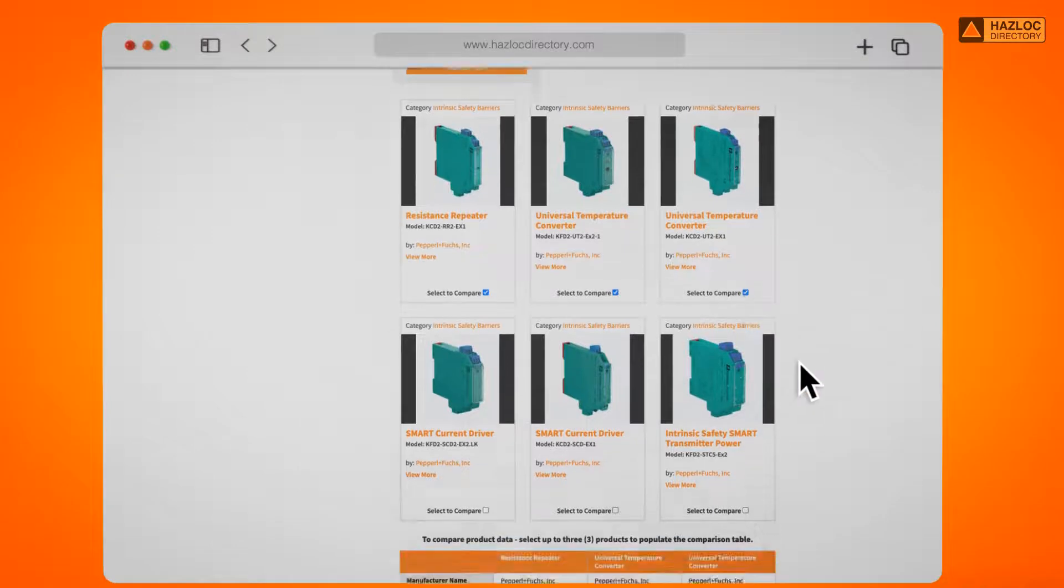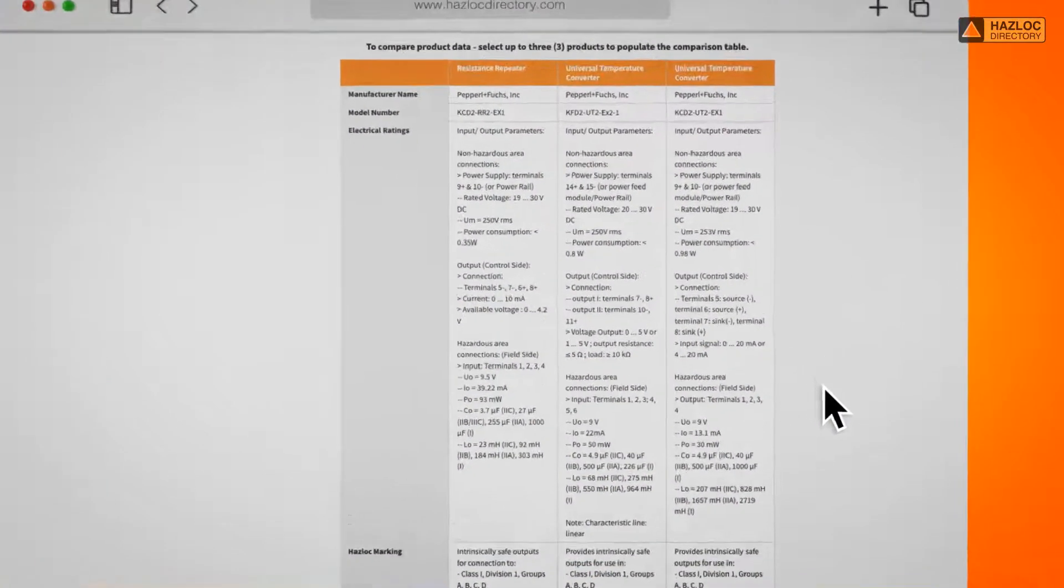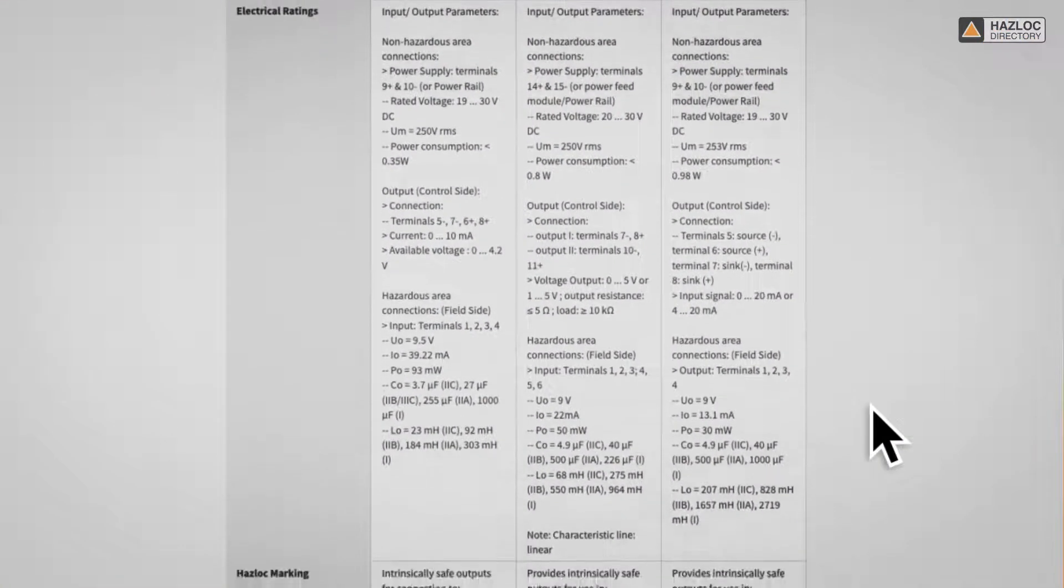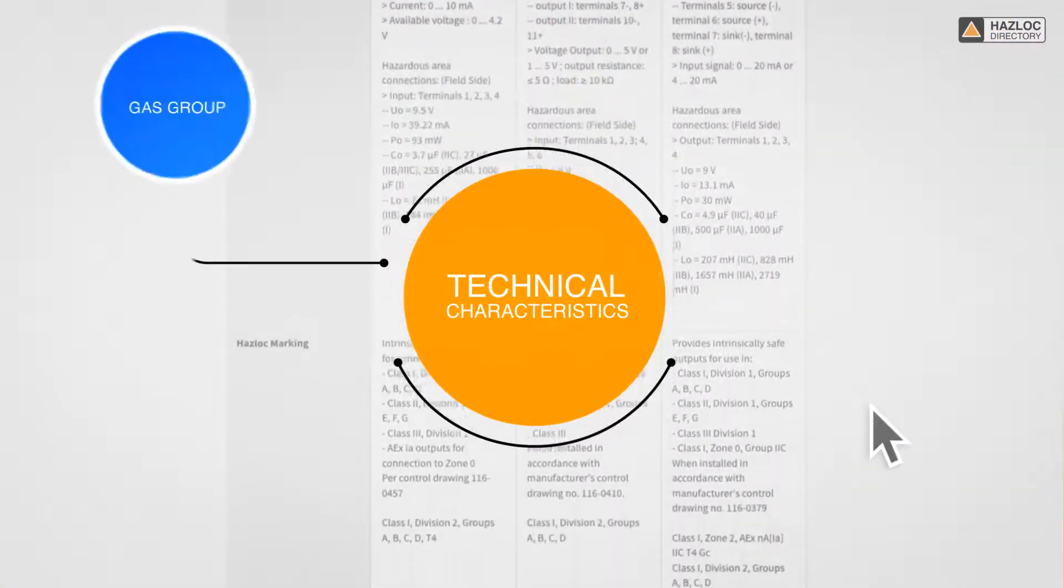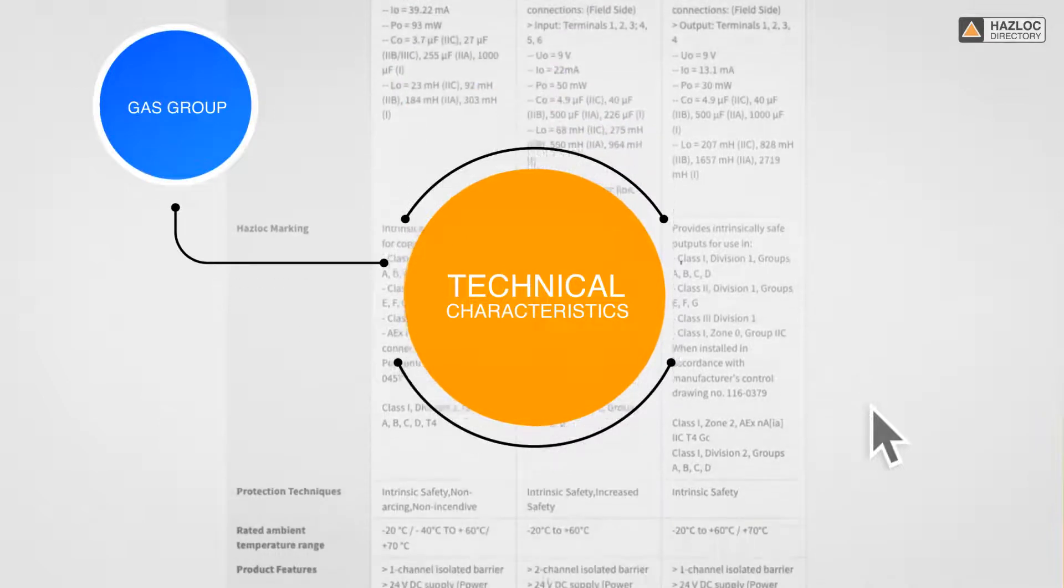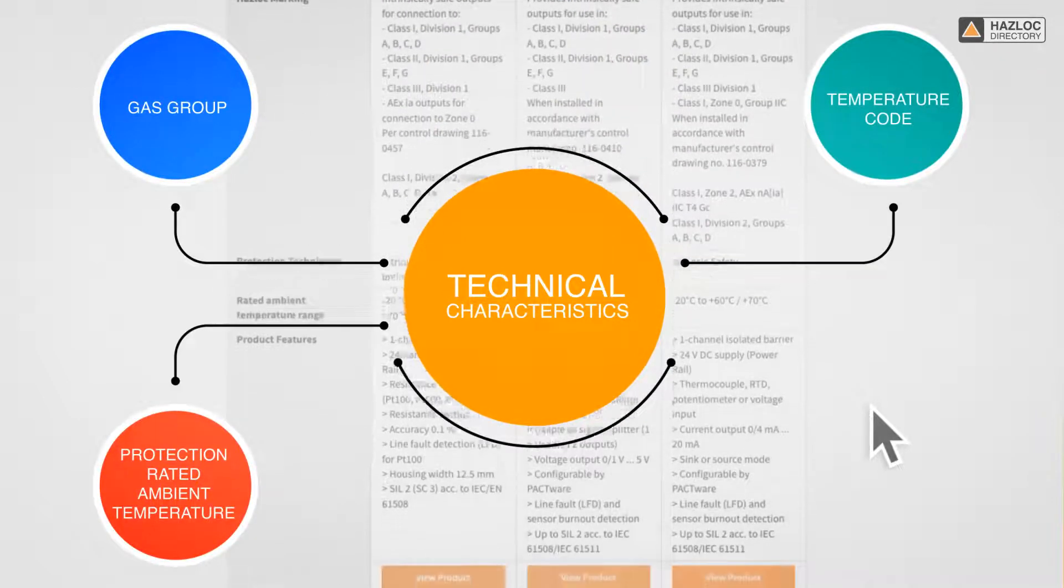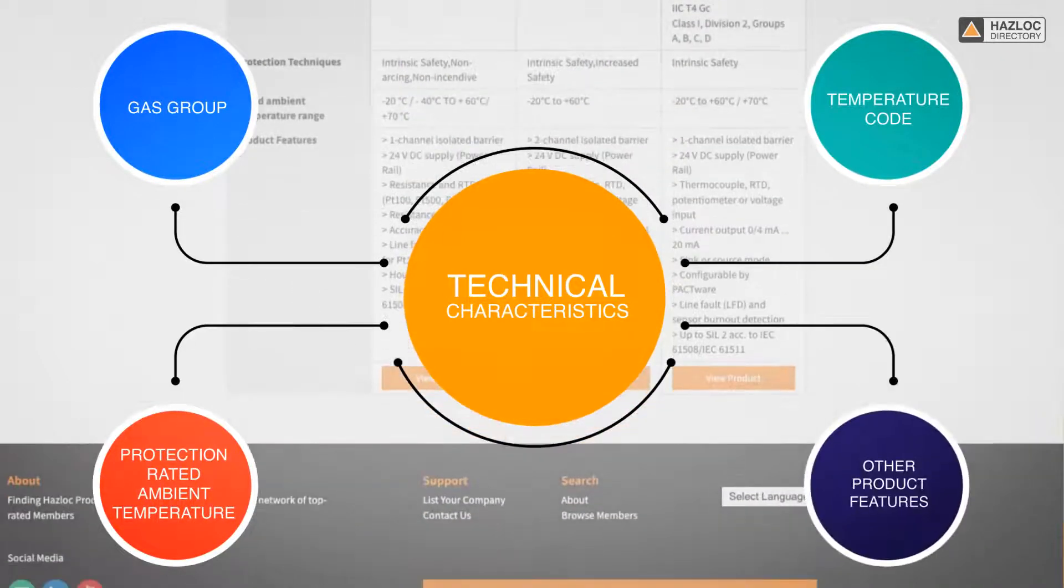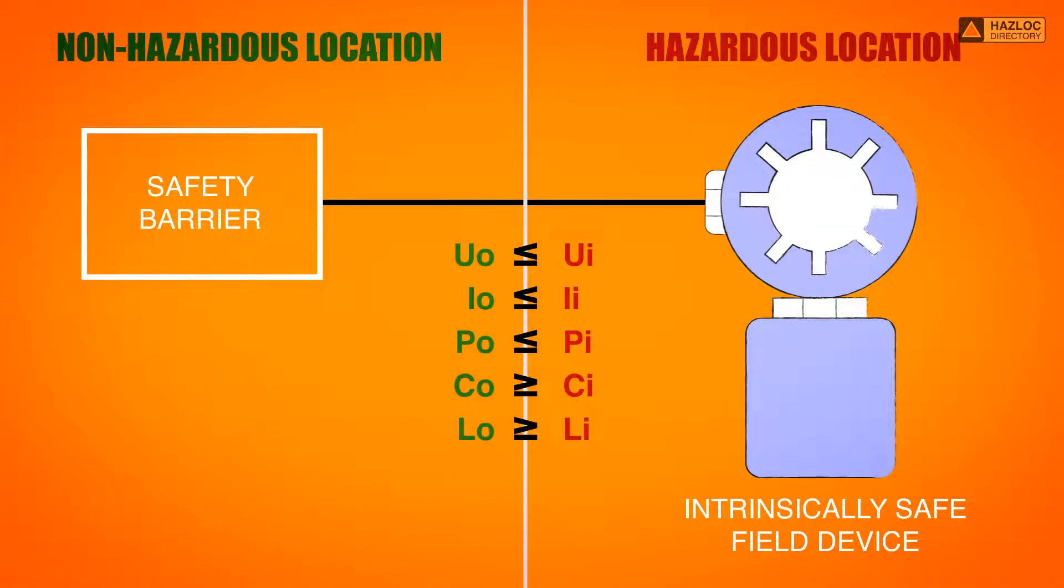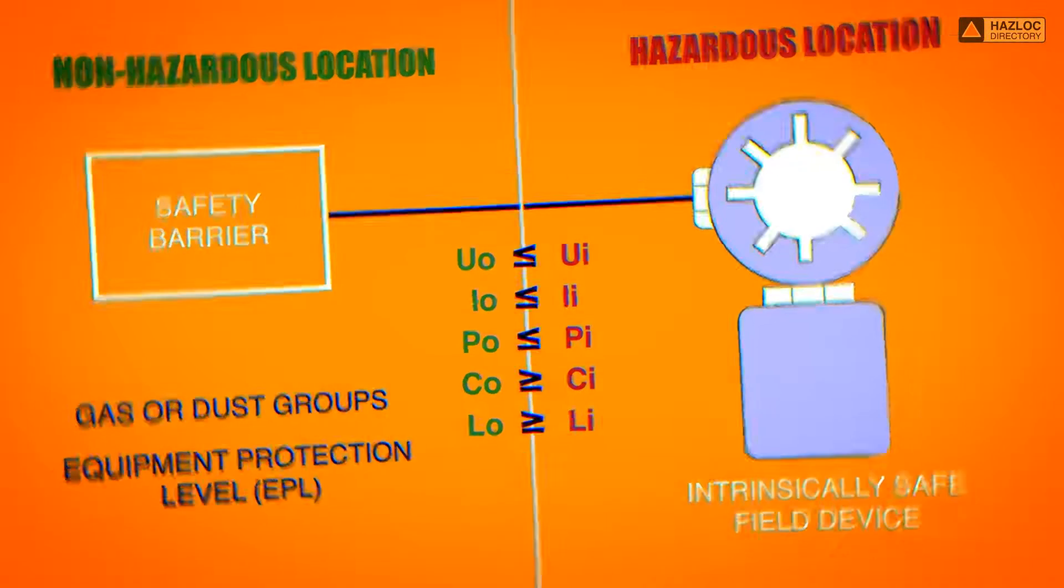You can also select three IS barriers from the search result and compare their technical characteristics, such as gas group, temperature code, protection rated ambient temperature, as well as other product features. Please remember that the compatibility of the selected safety barrier with your IS field device regarding the gas group or dust groups and the equipment protection level or EPL should be verified.